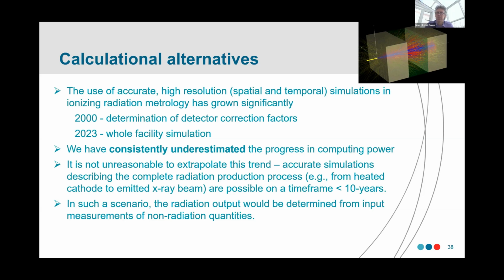But it wouldn't be unreasonable to say that, from an accelerator or an X-ray tube, just knowing some parameters of the power supply, we could simulate the output of the device. Absolutely. So, going crazy, just measuring the power into the power supply, it should be possible to give you the X-ray output at the end. So in this situation, you're measuring radiation output from non-radiation quantities, and in that context, you're traceable to the amp or the volt, not to the gray.